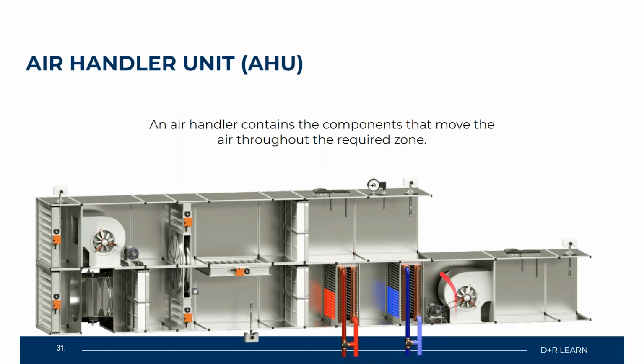So I veered off a little bit here, but the part I want to talk about on the air handler unit system is the coils. So remember, we spoke about the chiller system and the boiler system supplying hot water or chilled water to a coil that is going to then have air drawn across it in order to provide that heating or cooling to the space.